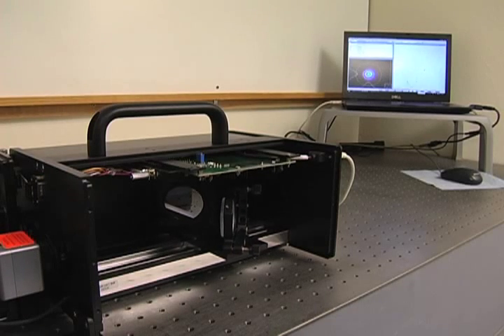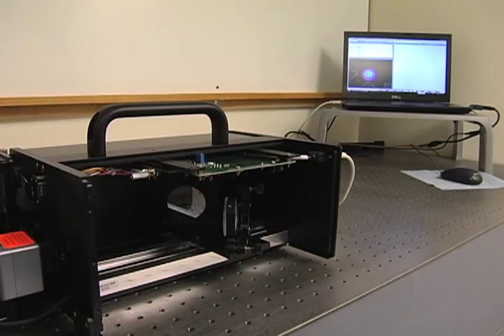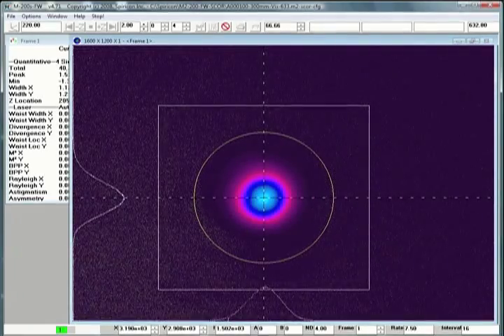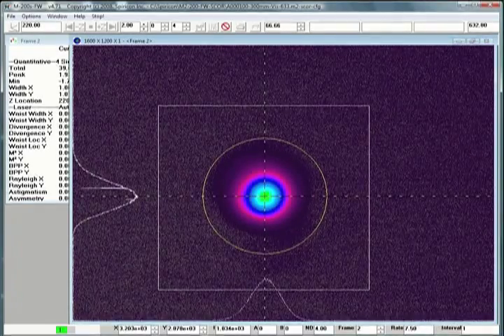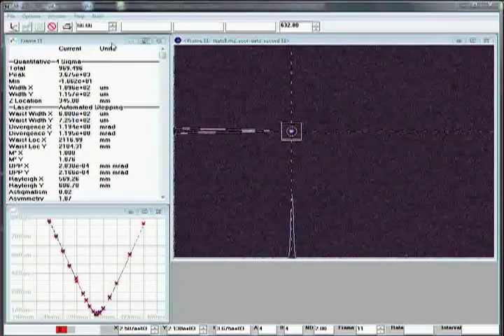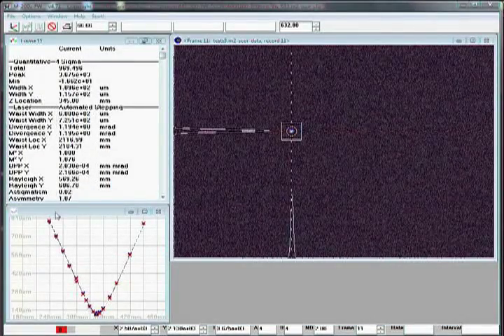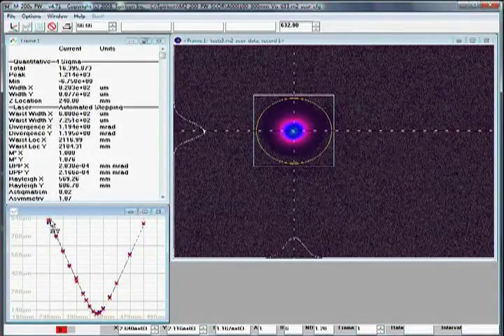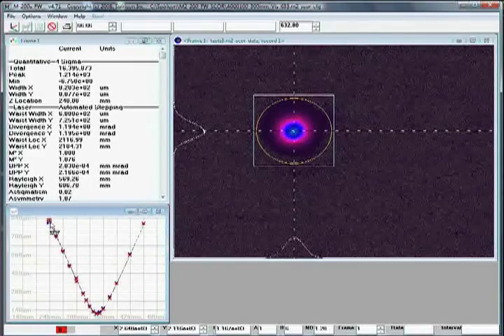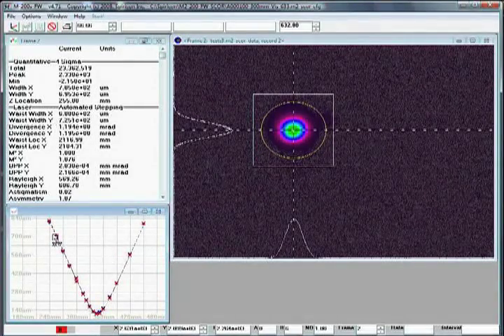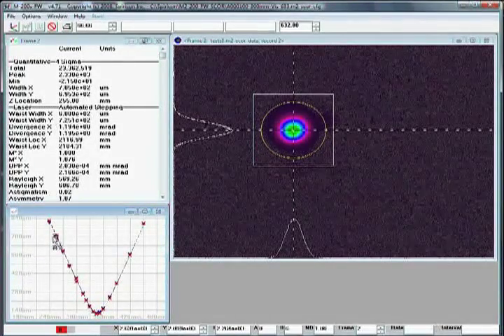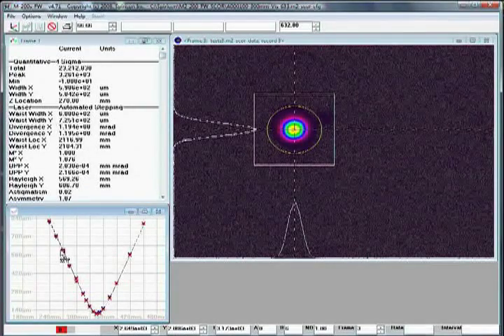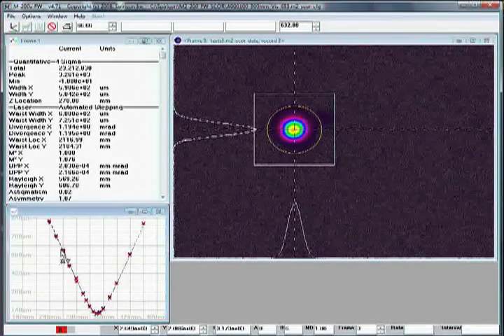During the measurement cycle, the software displays the 2D beam profile for the current sample point along the caustic. After the run, the user can click any individual sample and observe the beam profile, allowing visual, intuitive verification of the beam's behavior through focus.